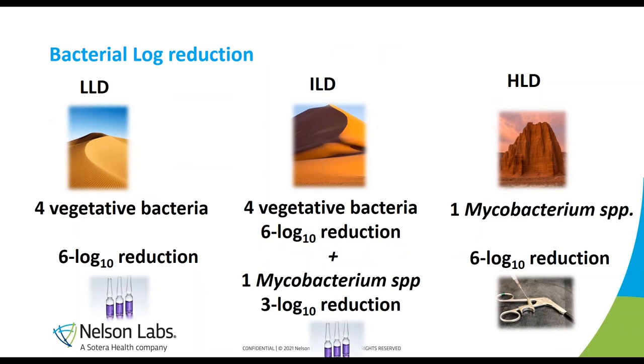For the bacterial log reduction approach: low level disinfection requires a 6-log reduction for four vegetative bacteria — E. coli, Pseudomonas, Staphylococcus, and Klebsiella species using ampules. Intermediate level disinfection requires a 6-log reduction for those four vegetative bacteria plus a 3-log reduction for one mycobacterium species. High level disinfection requires a 6-log reduction of a mycobacterium species, which must be a thermophilic mycobacterium highly resistant to heat.